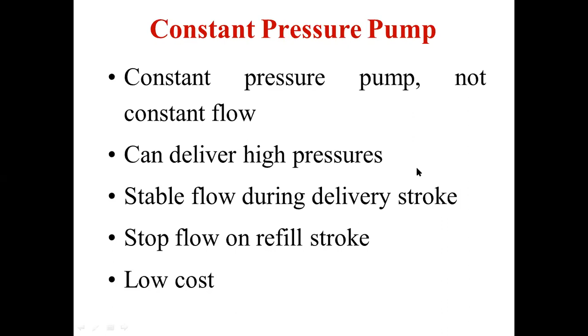There are two terminals. One is to the mobile phase reservoir and the other one to the chromatography column. A motor will be running always to create a constant pressure, but not the constant flow. You should remember, while creating this constant pressure, we cannot vary the pressure in between the separation. Once we adjust the pressure at 4,000 psi, the same pressure is going to be maintained throughout the separation while using this particular pump.